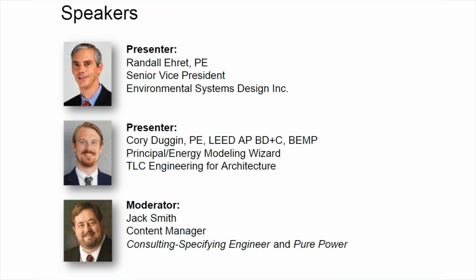Batteries will continue to charge, and we've got a fairly clean system to provide power. That also keeps it distinct and separate from the other branches, since we can't intermingle the life safety branch with other branches of the emergency power system. Another option that we see oftentimes is a UPS on one of the equipment branches, which is not required by code, but the owner often has data systems or other things they require to be on because of the functionality of their space and their building. And again, you need to separate that out and provide that through its own transfer switch because it can't be intermingled with the life safety loads.